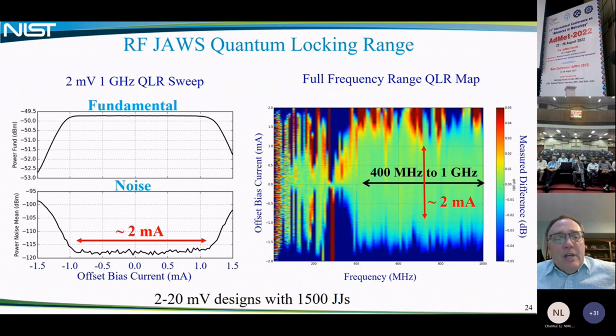We've been able to increase this output voltage now up to 20 millivolts, and this is getting close to the range to be useful for measuring components. We believe we can be useful for measuring components up to 50 millivolts or 100 millivolts. And the advantage of this system isn't necessarily its voltage accuracy, but its stability and reproducibility, and the fact that we don't have to have a calibration change to measure these signals as a source. They're intrinsically accurate.